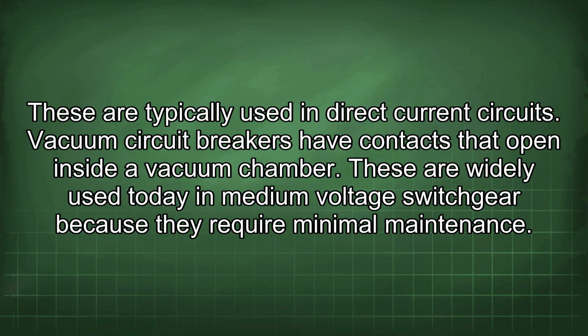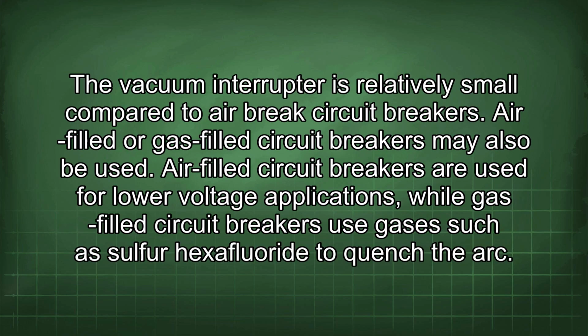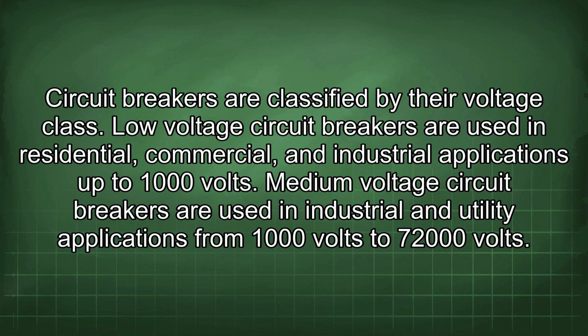Vacuum circuit breakers have contacts that open inside a vacuum chamber. These are widely used today in medium voltage switchgear because they require minimal maintenance. The vacuum interrupter is relatively small compared to air break circuit breakers. Air-filled or gas-filled circuit breakers may also be used. Air-filled circuit breakers are used for lower voltage applications, while gas-filled circuit breakers use gases such as sulfur hexafluoride to quench the arc. Circuit breakers are classified by their voltage class.